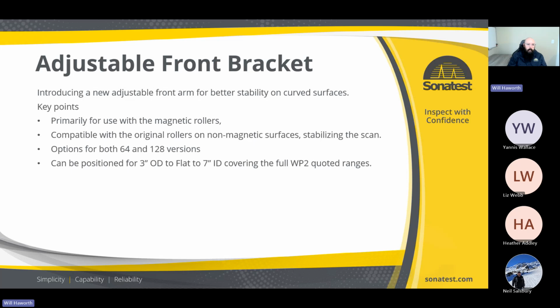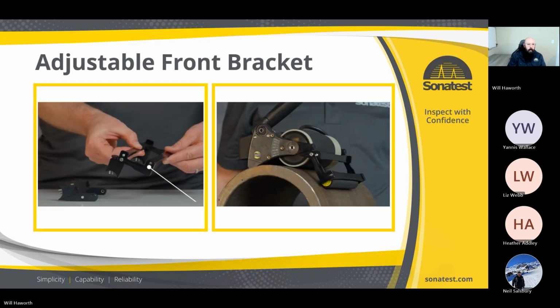Again, compatible with all of the wheel probes, 64 and 128. They will go down to 3-inch outside diameter and 7-inch inside diameter. So the front adjustable arm you can see here is adjustable, so it goes down and touches the pipe on smaller diameters, which helps hold the wheel probe on. Currently the regular wheel would just be sitting out in space, so this one will help hold the wheel probe up on smaller diameter parts.